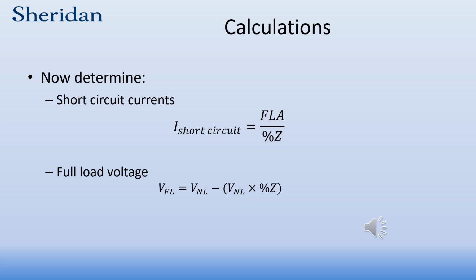Short circuit current, remember, is the current on the secondary of the transformer. That's where the load is. Short circuit current is equal to the full load amperage divided by that number we got by determining percent impedance. The full load voltage is equal to the no load voltage of the secondary minus the product of that no load voltage multiplied by the percent impedance, and that will give us voltage on the secondary under full load.